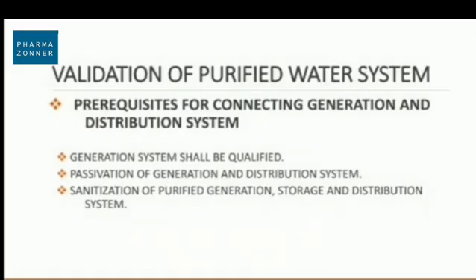Prerequisites before connecting the generation and distribution systems: the generation system shall be fully qualified first. Passivation of the generation and distribution system should be completed. Sanitization of the purified water generation, storage, and distribution system should be performed before connecting both systems.